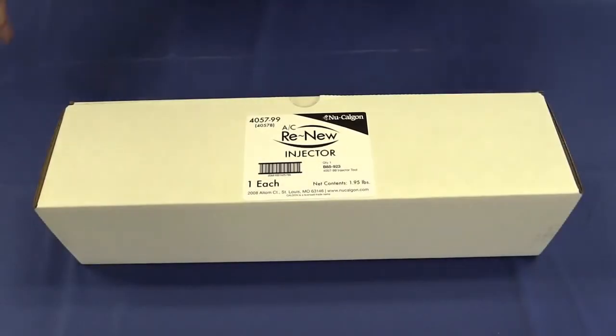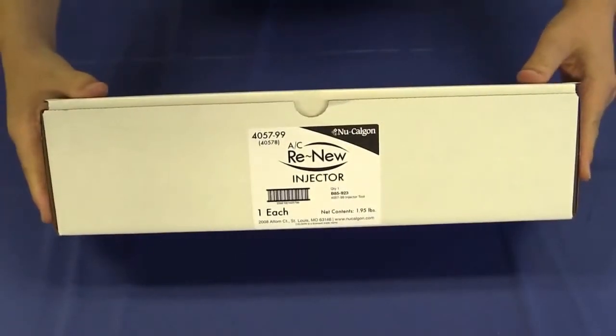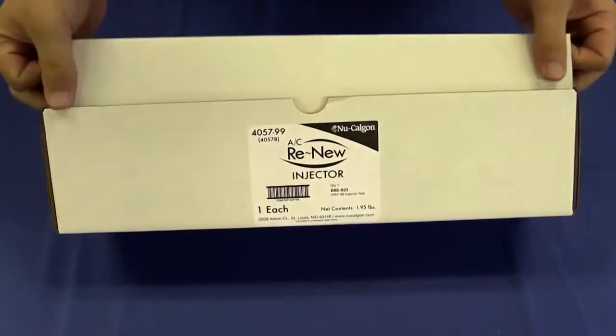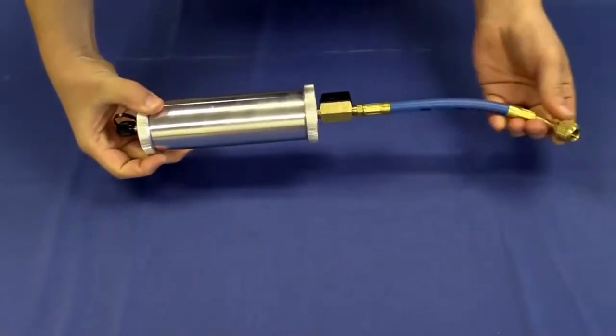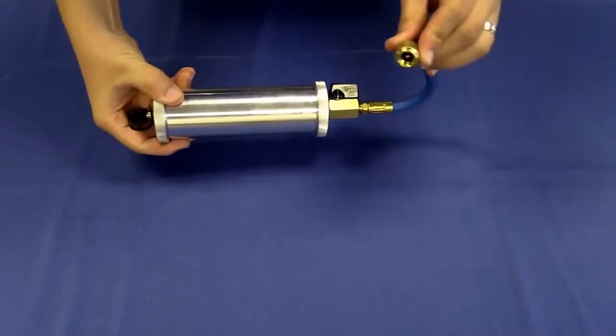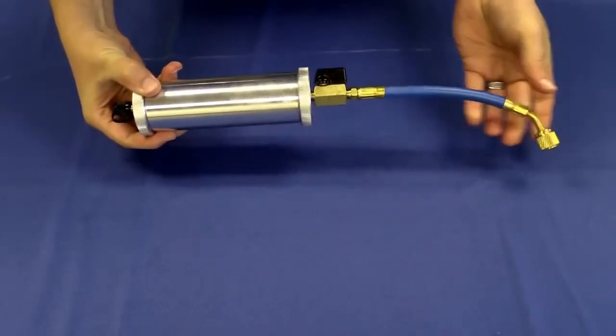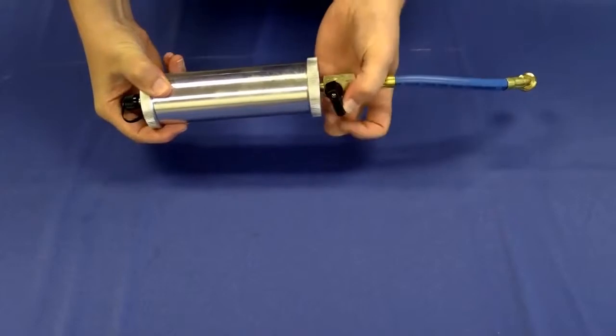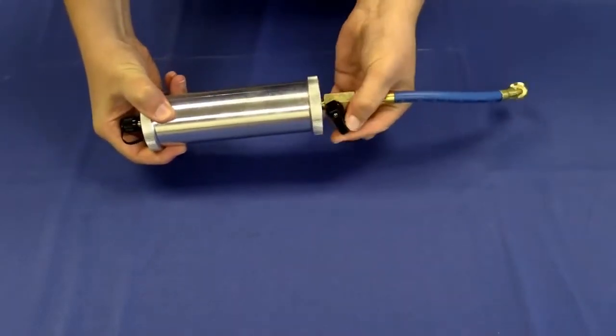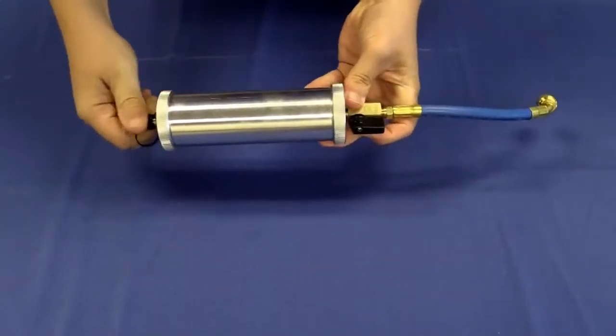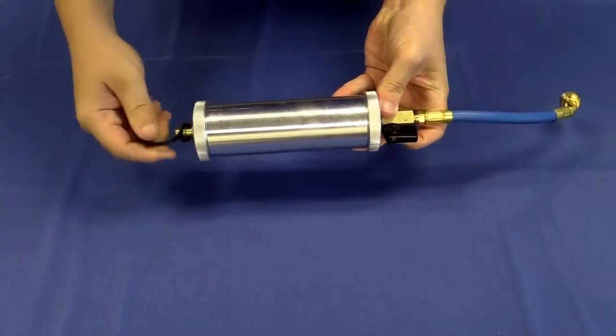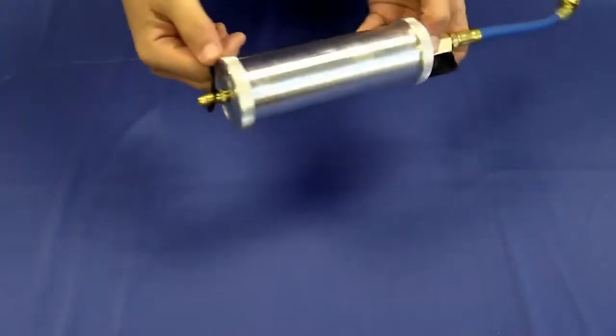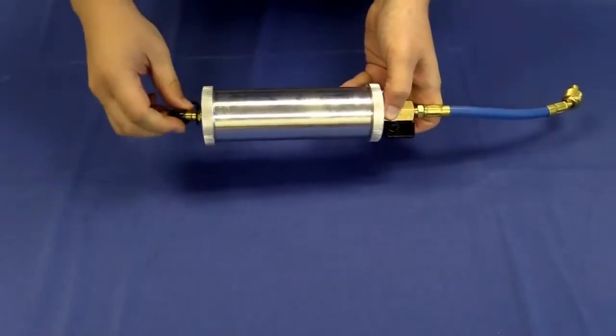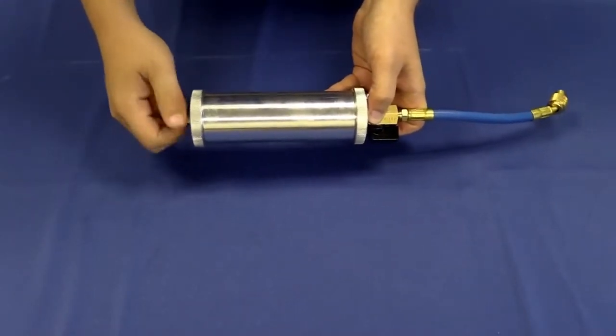The AC Renew injector tool was designed to inject AC Renew into air conditioning and refrigeration systems. It is constructed of rugged aluminum, has a capacity of 4 fluid ounces, and has a maximum working pressure of 600 psi. The AC Renew injector tool uses a core depressor connected to a short length of hose and a hand valve at one end, and a Schrader fitting at the other. In this video, you will learn how to use the AC Renew injector tool to safely and effectively install AC Renew as well as other injectable products.